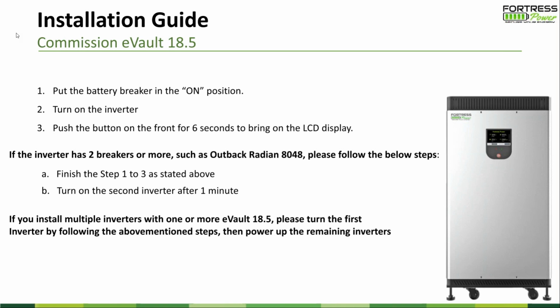We want you to put the system together, turn on the inverter, and then turn on the battery. Turning on the DC breaker doesn't mean you make the system live. We have to push the button in the front to start the BMS, and once the BMS starts working, that means the battery is live. We want you to wire up the whole system, put your circuit breaker in the on position, then turn on the inverter. Usually in this process, the battery will jump to the pre-charge circuit and charge up the capacitor in the inverter to make sure the inverter starts smoothly, and then jump onto the main circuit. The whole process takes up to 30 seconds. You will hear multiple clicks in the system, and then your system is commissioned. What if you have two breakers or more on the same inverter? For example, Outback.